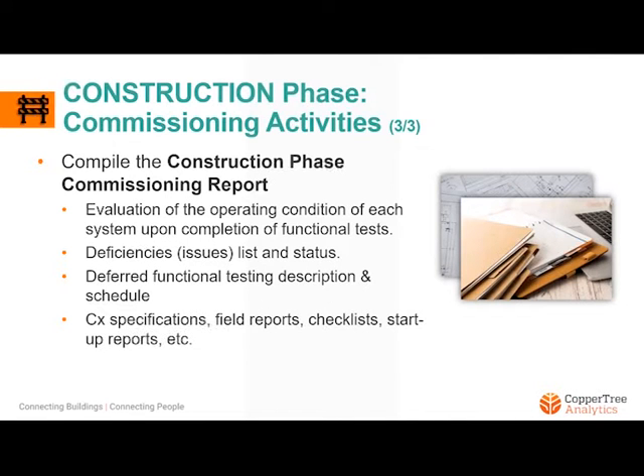Compile the construction phase commissioning report, which includes all of the previous activities leading up to this point. The commissioning report will include evaluation of operating condition of each system upon completion of functional tests, deficiencies list and status, deferred functional testing description and schedule, and commissioning specifications, field reports, checklists, startup reports, etc.